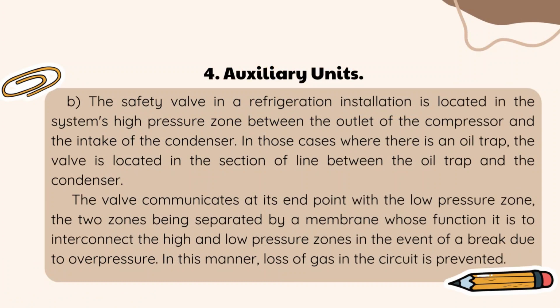B. The safety valve in a refrigeration installation is located in the system's high-pressure zone between the outlet of the compressor and the intake of the condenser. In those cases where there is an oil trap, the valve is located in the section of line between the oil trap and the condenser. The valve communicates at its end point with the low-pressure zone, the two zones being separated by a membrane whose function is to interconnect the high and low pressure zones in the event of a break due to overpressure. In this manner, loss of gas in the circuit is prevented.